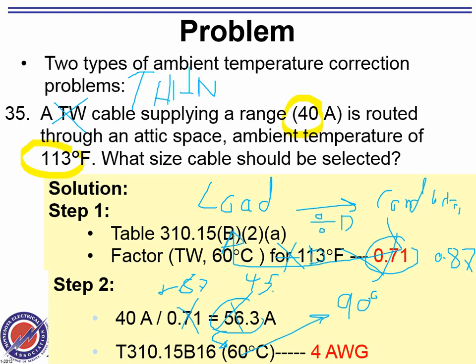45.9. Okay. Now go to 310.16 under the 90-degree column. Go to the 90-degree column. Give me the number that you got, the conductor that you got. How much? Number 8. Okay. Now do me a favor. Don't stop there. Now you're going to take number 8.